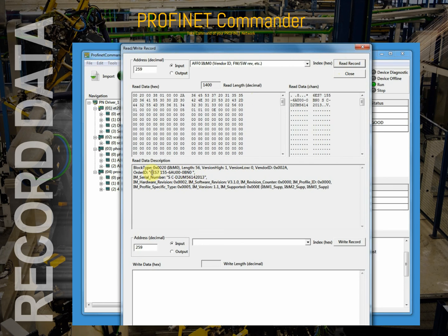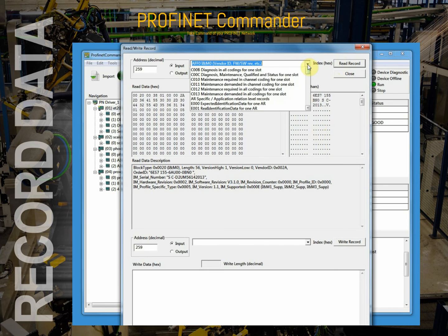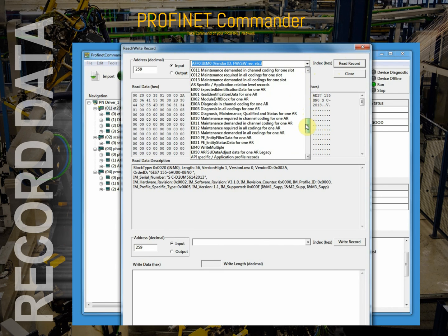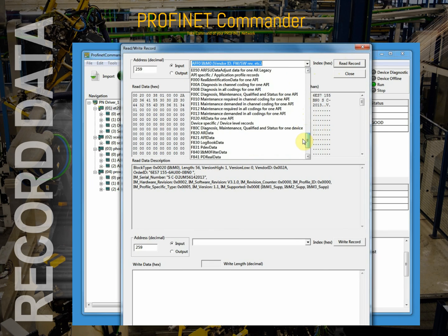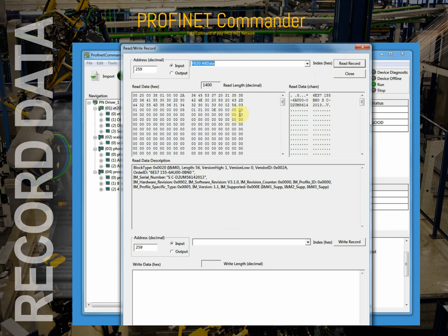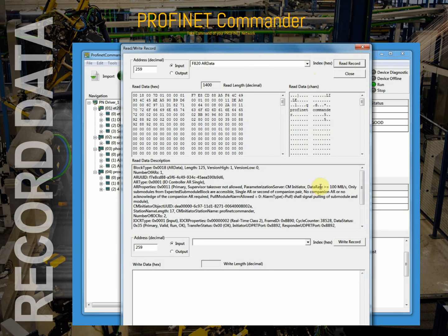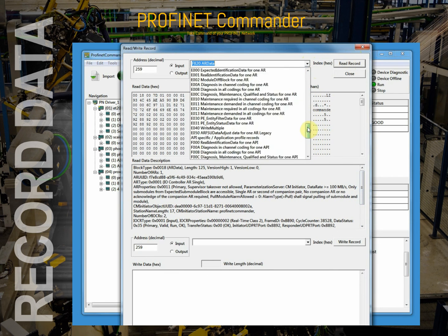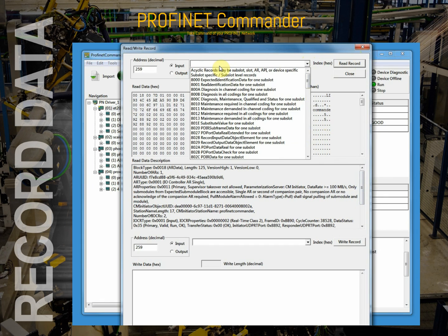I've got the part number, I've got the serial number, the software revision 3.1, and that kind of information. I also can get a lot of other information from devices, like statistics or diagnostic information, further diagnostics, further maintenance information. We can get information about our application in relation to the controller, for example, find out more about how that's set up. So again, there's a lot of different records PROFINET supports. All the standard ones are in here. And again, if you wanted to type in your own, which maybe was a vendor-specific record, you could do that as well, and then read data from that. Or you also can write record data from down here on the bottom window.